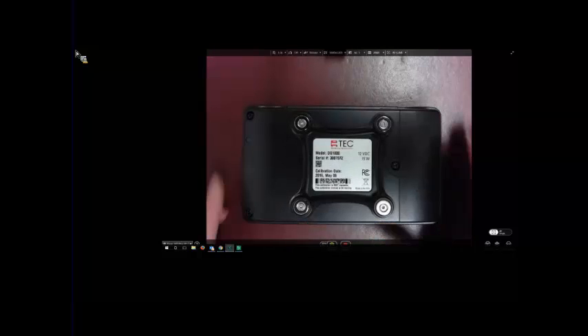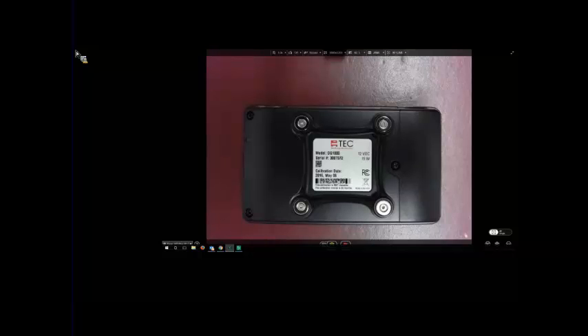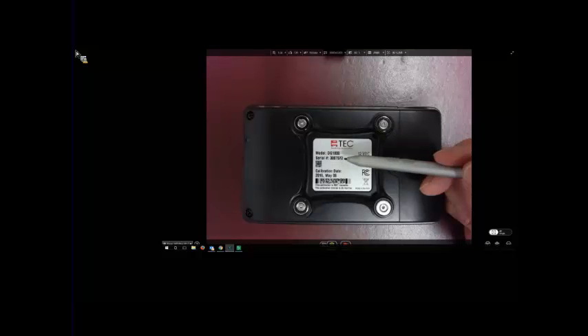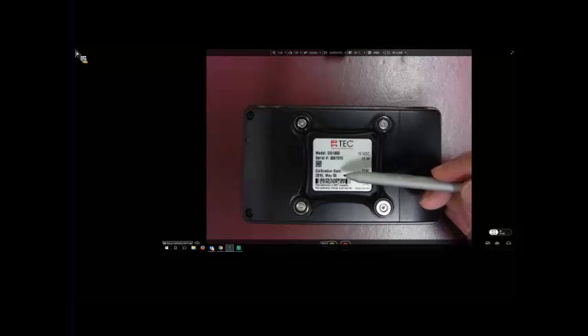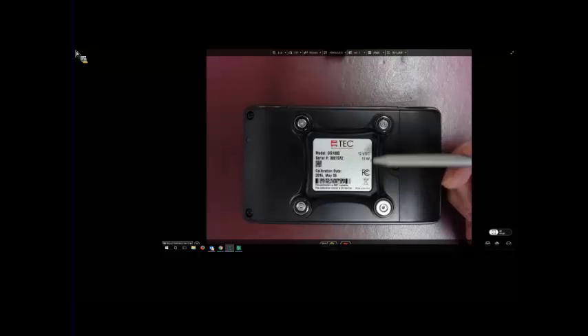So now when we turn the gauge over, you see the calibration sticker for the gauge, giving you the model number and serial number and the calibration date, the fact that this is NIST traceable, and that the calibration interval is 24 months. We've added some barcoding here for us so that when we do have instruments coming back and forth, we're able to track them a little bit more easily.